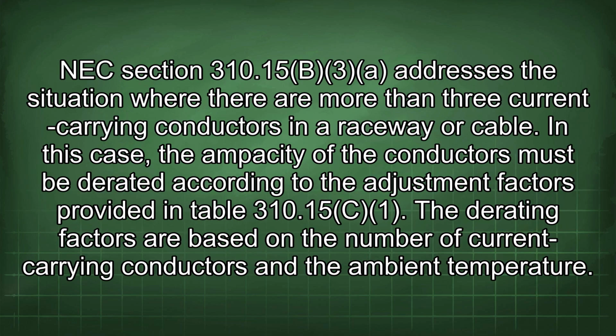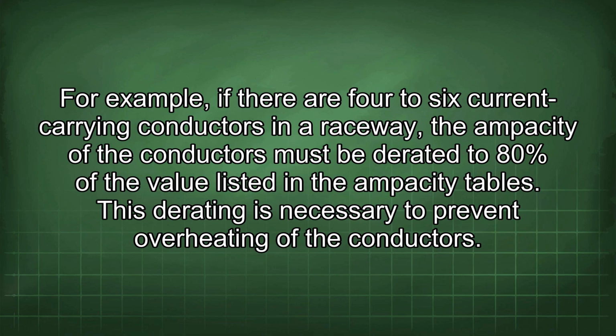NEC section 310.15(B)(3) addresses a situation where there are more than 3 current carrying conductors in a raceway or cable. In this case, the ampacity of the conductors must be derated according to the adjustment factors provided in Table 310.15(B)(3)(a). The derating factors are based on the number of current carrying conductors and the ambient temperature. For example, if there are 4 to 6 current carrying conductors in a raceway, the ampacity of the conductors must be derated to 80% of the value listed in the ampacity tables. This derating is necessary to prevent overheating of the conductors.